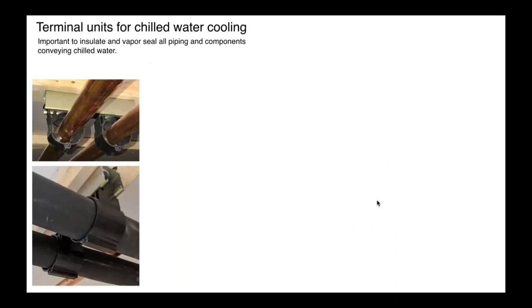Okay, here's a piping detail. These are some pipe support brackets for copper tubing that allow the insulation to basically slide right into the center point. They support the weight of the pipe, and you can see that's on a strut channel right here, but it allows you to slide the insulation in from both sides. And it's just a very small little, it's probably less than an eighth of an inch thick polymer wall where these two ends of the insulation will meet. So you get good mechanical support. And if you caulk that detail, we haven't shown it here, but if you caulk that up with some silicone, you're basically going to keep any air away from that joint.